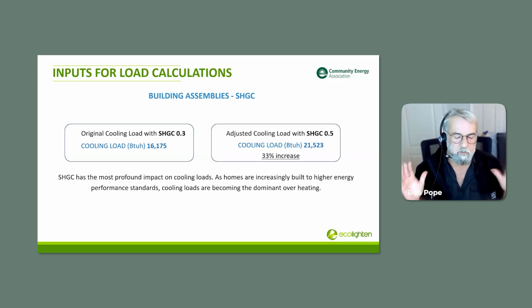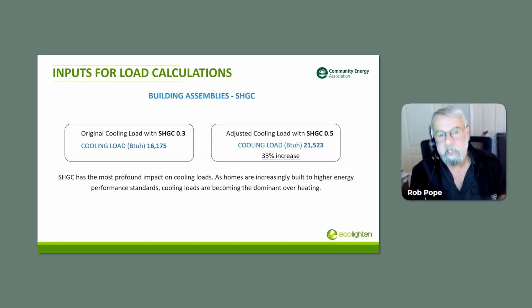As we get better at building homes, they're more high performance than they ever were - less drafty. We have the ability to keep the heat in, which is designed for winter conditions, because we're in Canada, and we're much better at keeping the heat in. The problem happens in the summer. We still have the same internal gains - same lights, more equipment running, monitors, computers, and whatnot. We still have solar gain from the windows. We haven't changed that cooling part of it very much, so we still have substantial heat gains. Yet we don't have the same ability that we used to in older homes to dissipate that heat to outside - it's stuck inside more. So increasingly, cooling loads have become the more dominant loads, and it'll continue to do that, especially with the way the climate's changing.